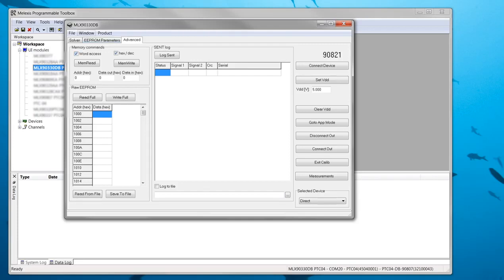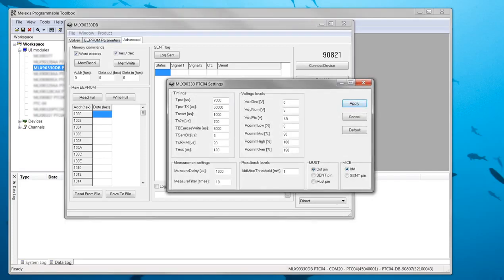The settings are open from the window menu at the top. In this demo, I am using the sent output, so sent should be checked in the bottom right. In case the analog output is used, out should be checked instead. While in the settings window, I also increase the measure filter at the left, because when logging sent, this setting decides how many frames are decoded. If instead of the sent logging function the measurements window is used to plot pressure and temperature, the filter should be set to 1.